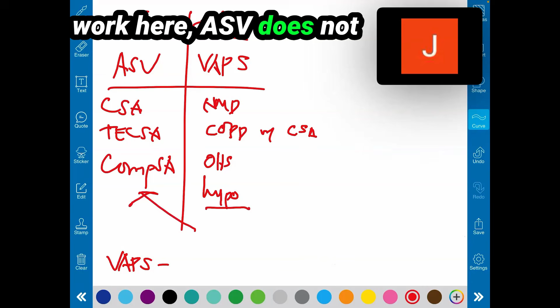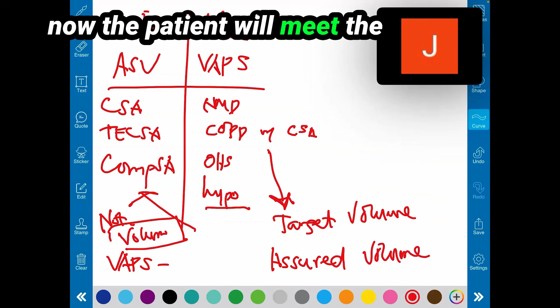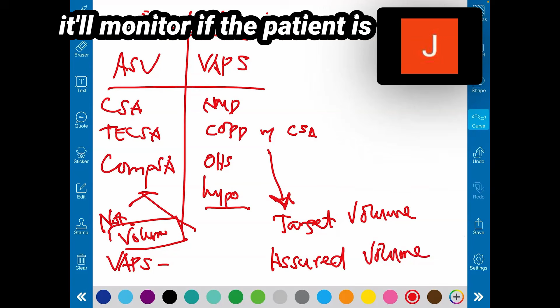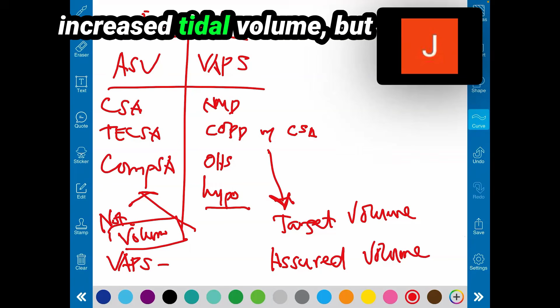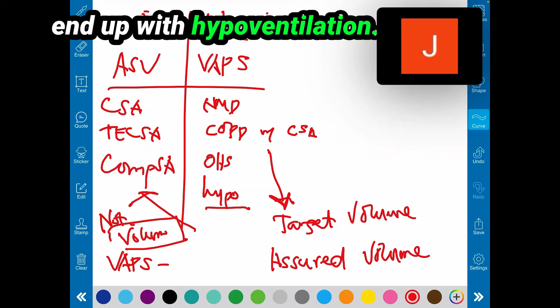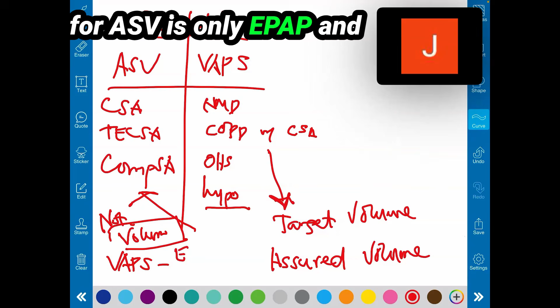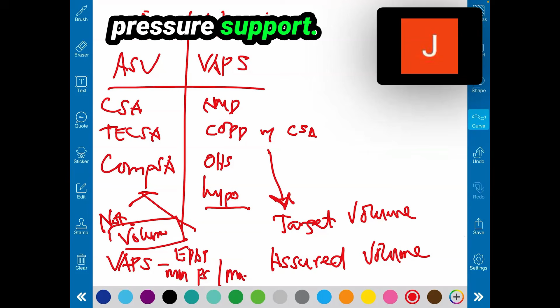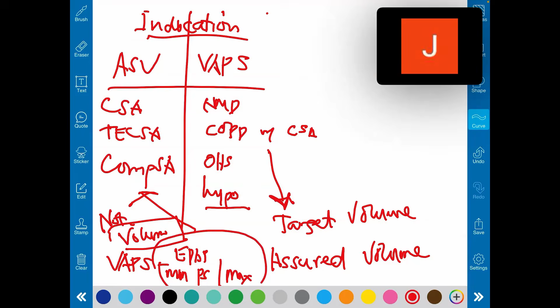ASV does not have assured volume. Okay? Dito, it will have a target volume. The device will make sure that the patient will meet the right volume every breath. Whereas the ASV will not. It will monitor if the patient is having a central or having an increased tidal volume, but it will not protect them if they end up with hypoventilation. The setting for ASV is only EPAP and then minimum pressure support and maximum pressure support. That's it. There's no way to protect the breath.